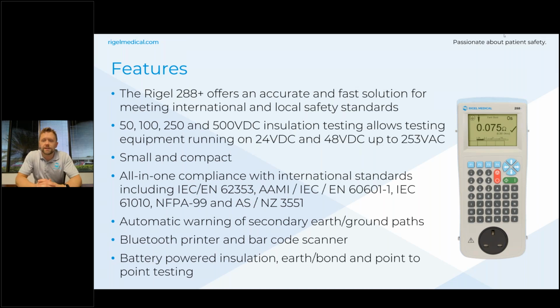Driven through the battery, but for any leakage tests, for a ground leakage, enclosure leakage, then obviously the device needs to be plugged in. We've got multiple configurations of this unit. You can see on the front there, that socket might not be as recognizable to some people in the US, but we do have a US specific device for this 288. We've got a full range of insulation testing, so that allows you to test low voltage equipment down to 24 volts and also up to 250 volt AC voltages as well.